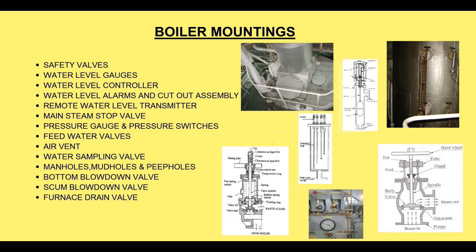Boiler safety valves: these are fitted to protect the boiler against overpressure. They are fitted in pairs on the steam drum and designed to open at a designed blow-off pressure. For boilers with superheaters, one more safety valve must be fitted to the superheater outlet header. Main steam stop valves are fitted to isolate the main steam supply line, usually of non-return type. Feed check valves allow feed water to enter the boiler and prevent back flow of water in the event of feed water pump failure. Water level indicators are required to see the water level of the boiler.